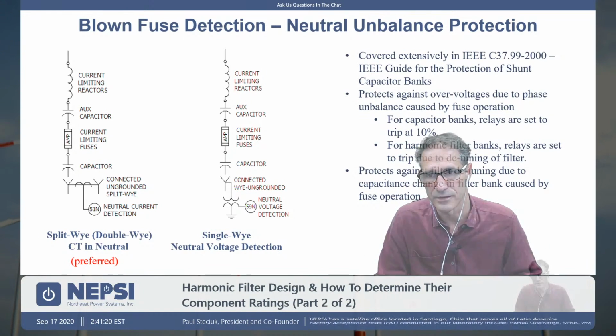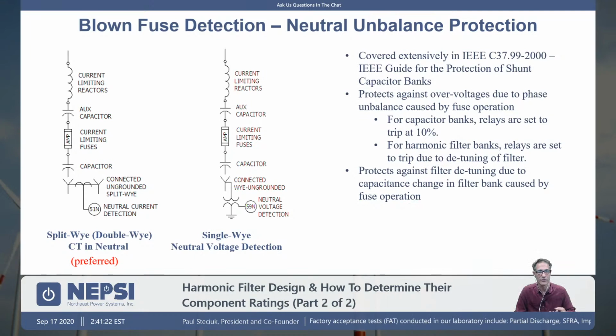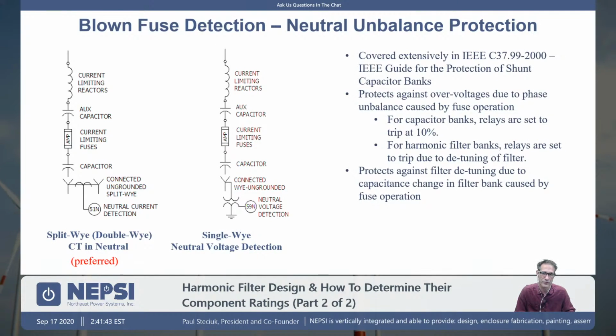And it's that current flow that would indicate that I have an unbalanced condition, and that unbalanced condition is causing current flow. And we have on our website a tool. Go to the resource section on our webpage. There's a spreadsheet tool on our website that will help you calculate what that neutral current is for medium voltage cap banks. We do prefer the Split-Wye connection.